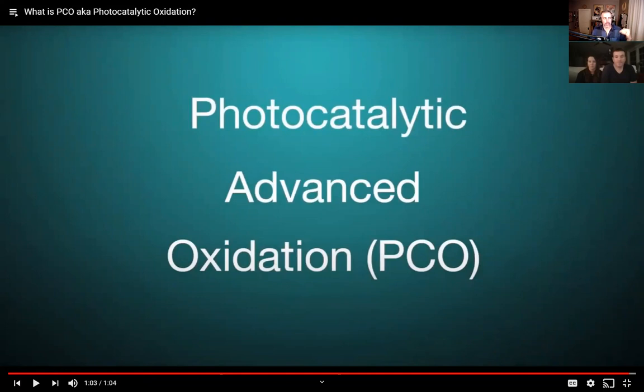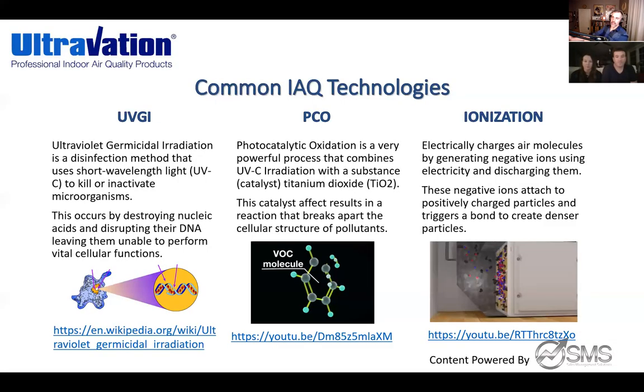The only thing left behind is trace amounts of water vapor — nothing harmful. PCO adds another layer beyond what UVC light is already doing. From a UV perspective, you don't want a naked eye looking at UV light, especially the UVC frequency — you could literally burn your eyes. That's why these products are installed inside the ductwork. As the air passes through 24/7 while your HVAC system is running, it passes through these invisible fields.